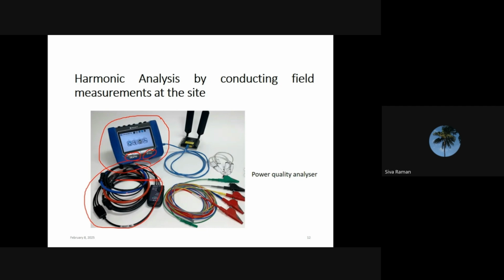Normally we studied that current transformers are mostly of the electromagnetic type. These CTs are not electromagnetic type. These CTs are Rogowski type. Rogowski coil, that is the Rogowski principle. So these CTs are manufactured based on the Rogowski principle. These are for the current measurement, these for the voltage measurement, and these cables for communication purposes. Nowadays, we can monitor the power quality analyzer from a remote location whenever it is connected through Wi-Fi or an Ethernet line like this.